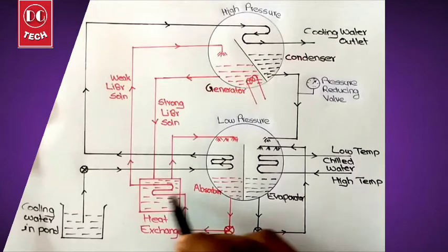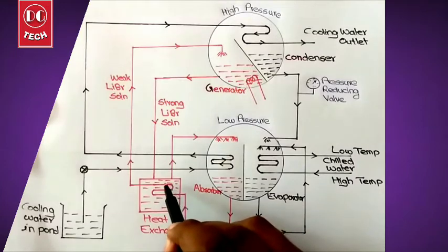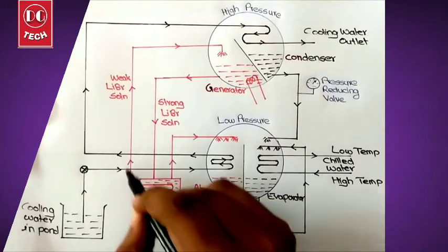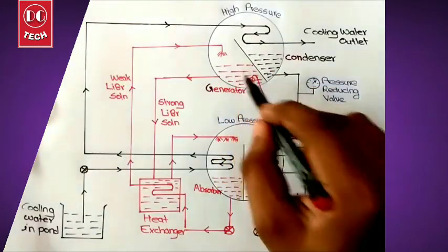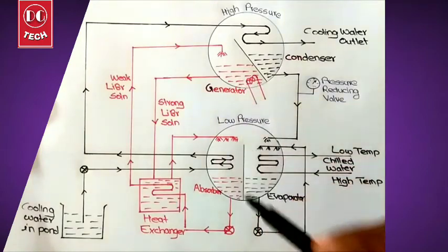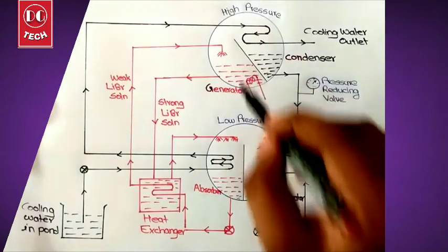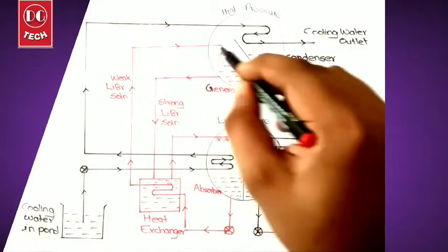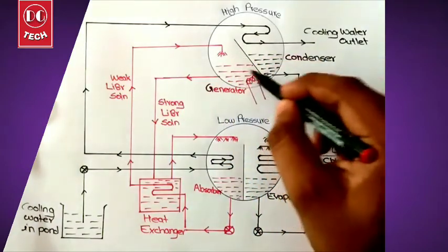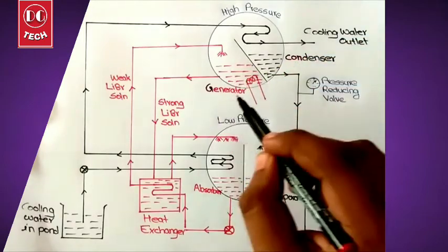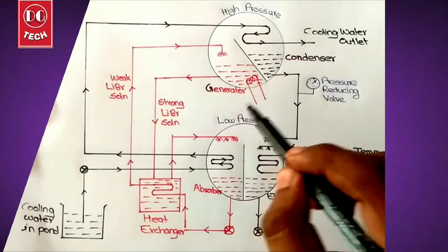The weak lithium bromide flows through the heat exchanger, absorbs heat from it, and moves towards the generator. In the generator, a coil is used to increase the temperature of this solution. The weak lithium bromide is sprinkled and the generator increases its temperature.